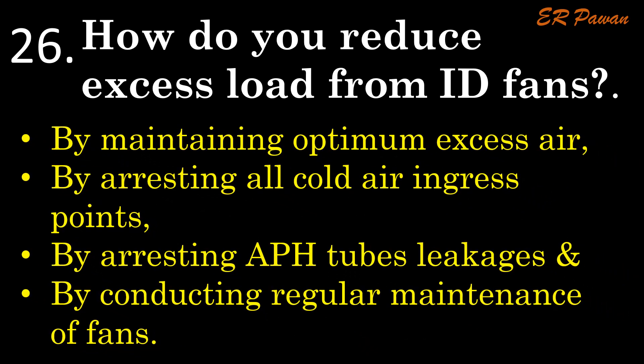Question 26: How do you reduce excess load from ID fans? By maintaining optimum excess air, by arresting all cold air ingress points, by arresting APH tube leakages, and by conducting regular maintenance of fans.